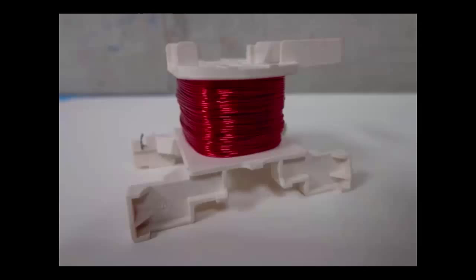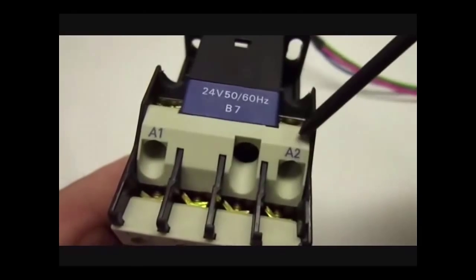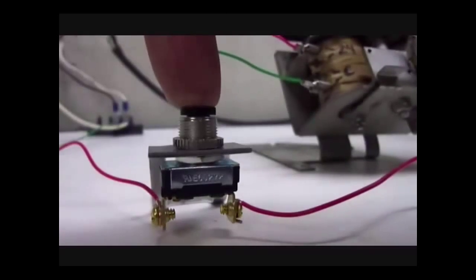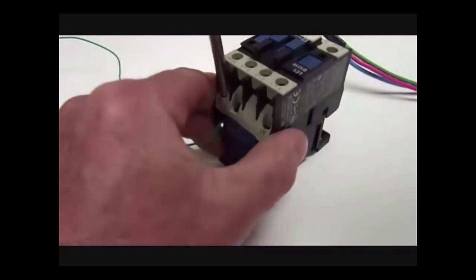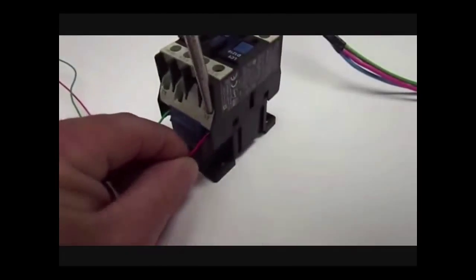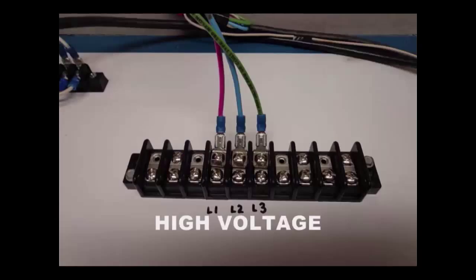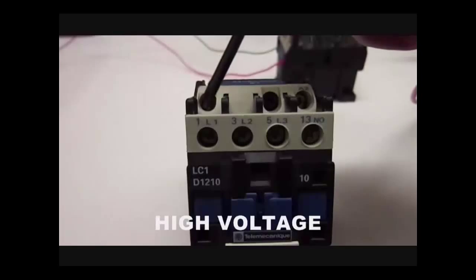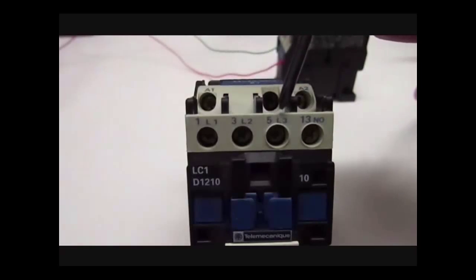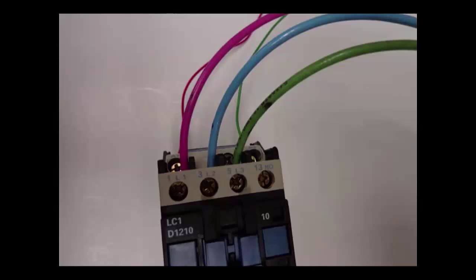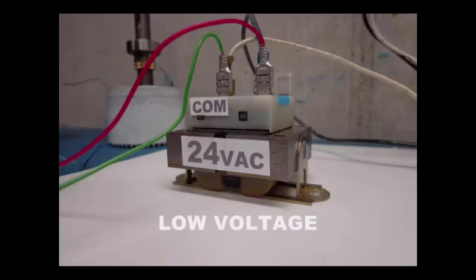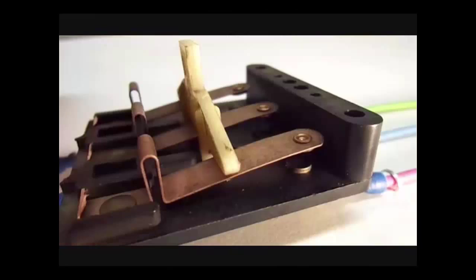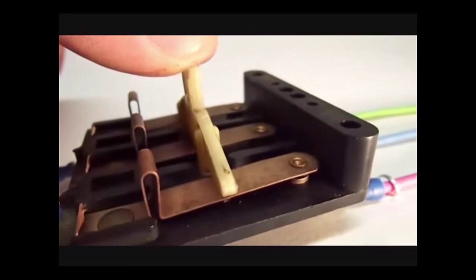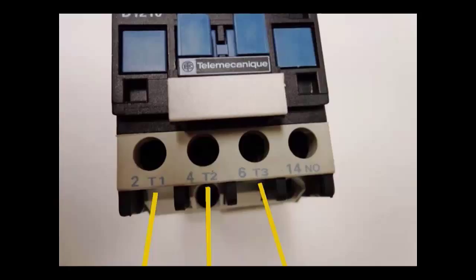I'm going to connect 24 volts to the coil terminals labeled A1 and A2 with a push button to start and stop it. Polarity on the coil terminals doesn't really matter. I'm going to bring my 3 phases from the breaker panel into the terminals labeled line 1, 2, and 3. Now we have constant power coming into the contactor, and when I connect 24 volts to the coil, it will allow that power to go through the main contacts to terminals T1, T2, and T3. I don't know what T stands for, but I know it gets hooked up to the load.